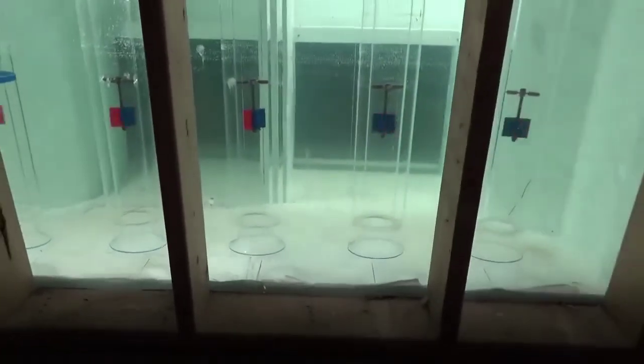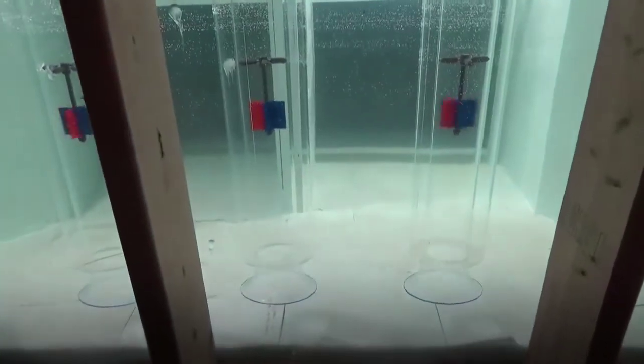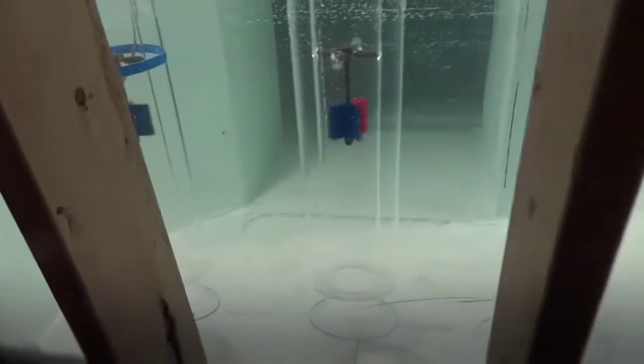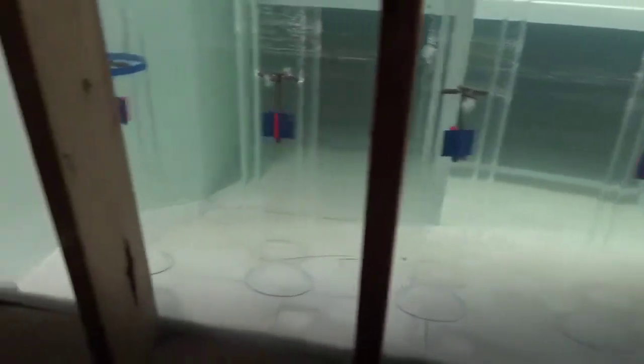Let's go to a 4-pump. Okay, so 4 pumps here. Let's take a look at that. Okay, so 4 pumps running. Pre-swirl again just remains very, very high. Watch that just spinning right here. Let me get the value for that. And we're looking at the order of about 10 degrees on this pre-swirl, which is significant.